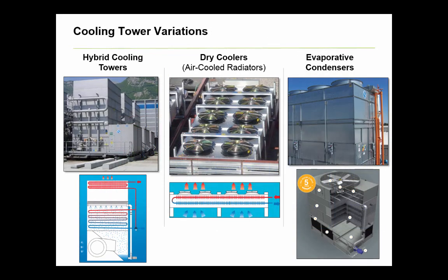Lastly, although not within the detailed scope of this video, it should be mentioned that there are alternative designs that can be used to reject heat to the atmosphere, such as hybrid cooling towers, dry coolers — also known as air-cooled radiators — and evaporative condensers. Each has its application specialty, such as air-cooled radiators being used in regions where water is a more valuable resource than energy, meaning they cost more to operate but use less water. Effectively, each of these variations does the same job as an evaporative cooling tower by doing the final rejection of building heat to the atmosphere.